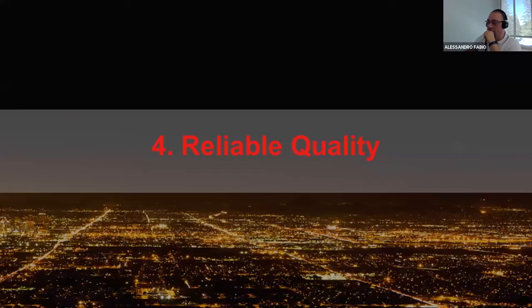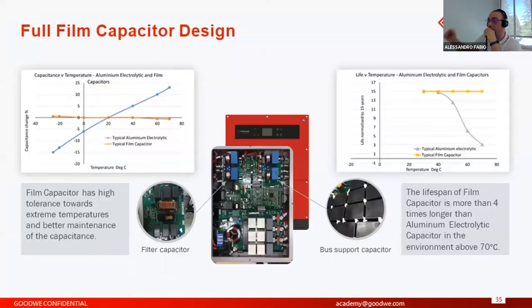So, reliable quality. I want to speak about the technology that we use. For example, we use film capacitor technology inside of our inverter, and not the standard aluminium electrolytic capacitors. With film capacitors we can increase our performance and our efficiency, because at 70 degrees, for example, the aluminium electrolytic capacitor technology is too old at the moment, and it can reduce the efficiency and also the life of the inverter. So we use film capacitors to increase our performance, our efficiency and also the life of the inverters.